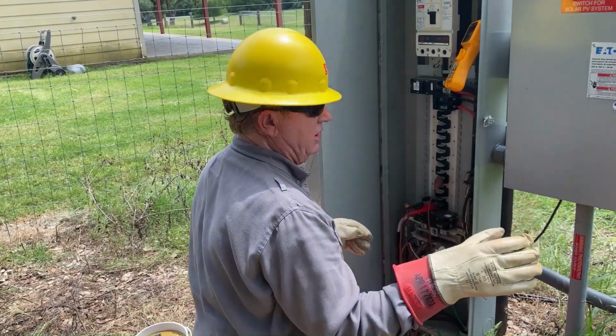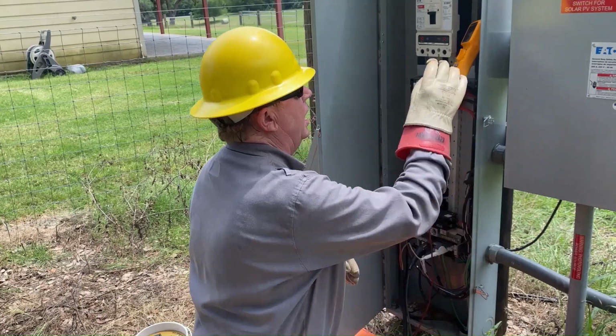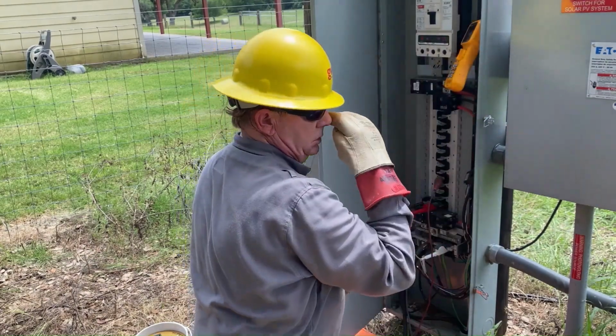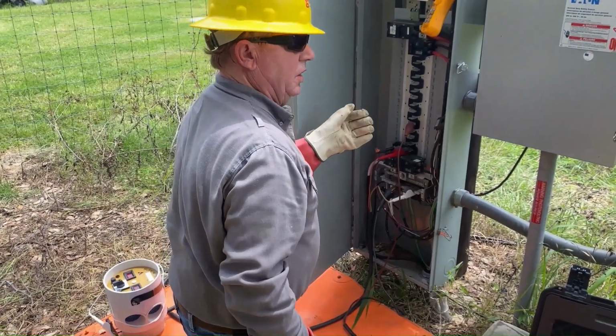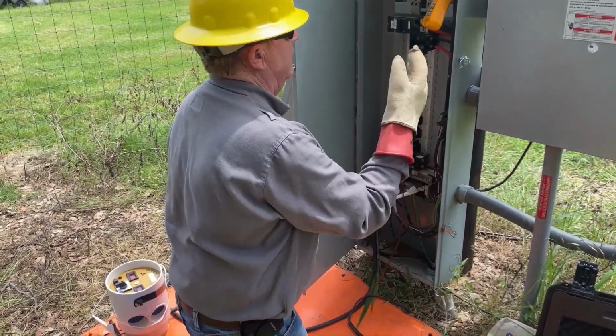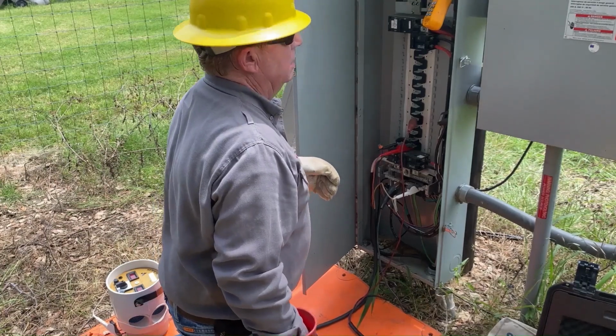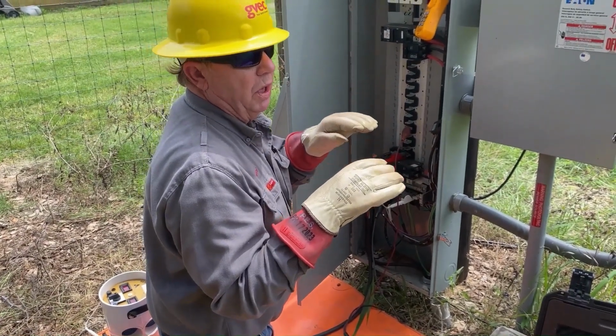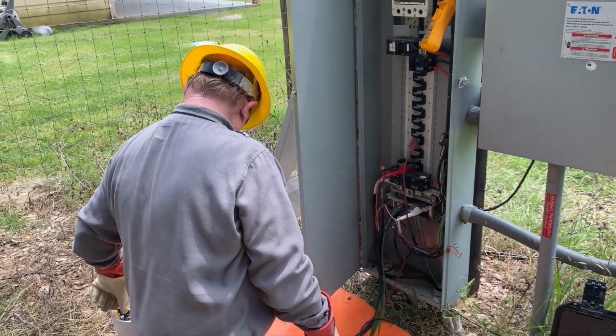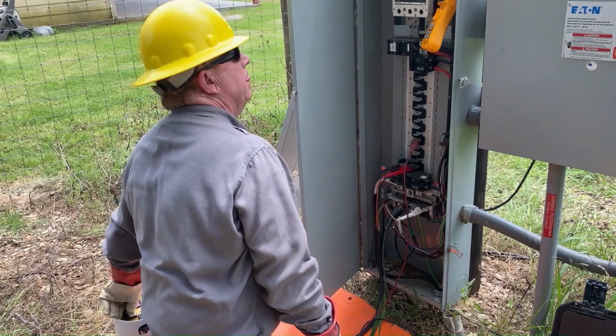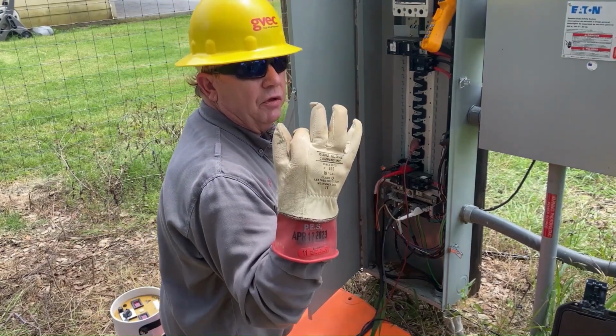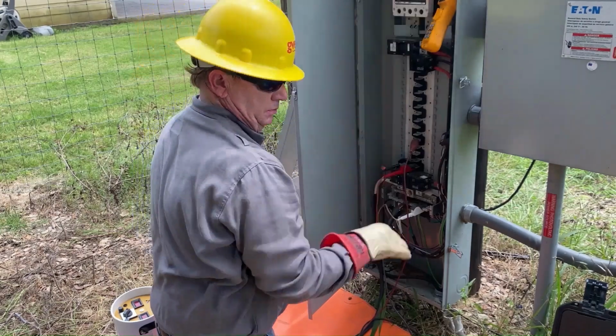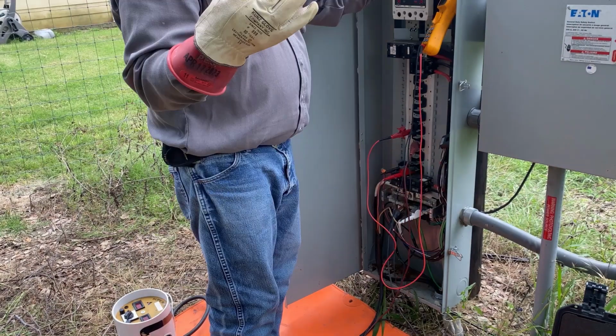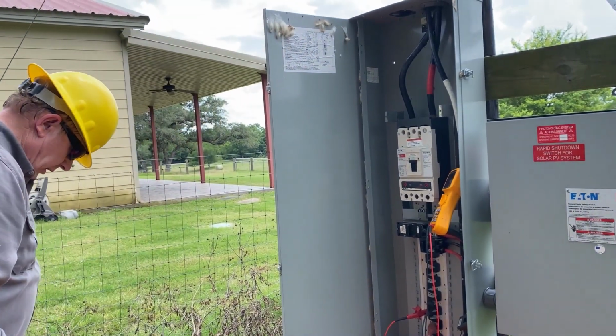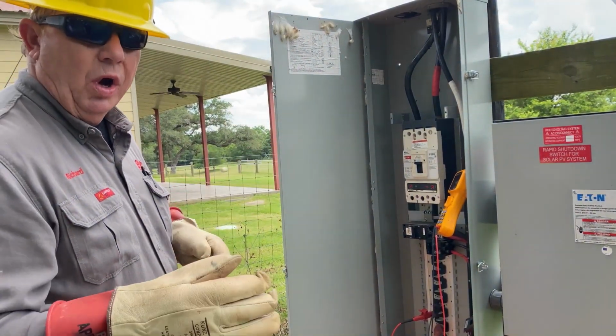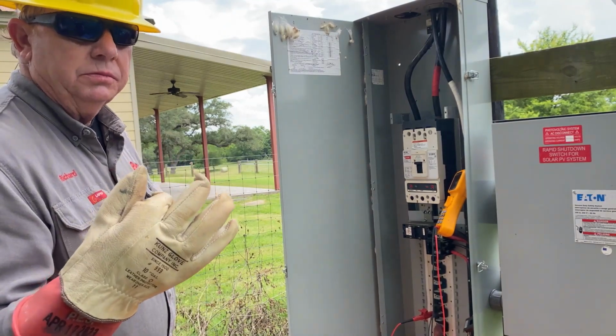As we move 26 amps on this side, and it looks like 20, we had 4 amps on the neutral up here. So we had 120 volt load, 120 volt load, and when they're both running, we have 4 amps on the neutral. The voltage is pretty steady at about 121, 121. We're going to go ahead and let that cook. That's 3 amps on the neutral up here. 3 amps on the neutral. I'm 124 and 118 with 3 amps on the neutral.